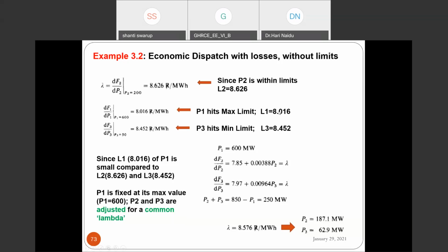In economic operation, the incremental fuel cost should be very low - look at this, this is the logic. Since L1 of P1 is small compared to L2 and L3, P1 is fixed at its maximum value. I fix P1 at 600 because L1 is the lowest. Then I adjust unit 2 and unit 3 - they'll have a common lambda.